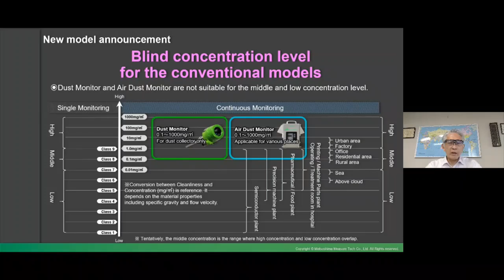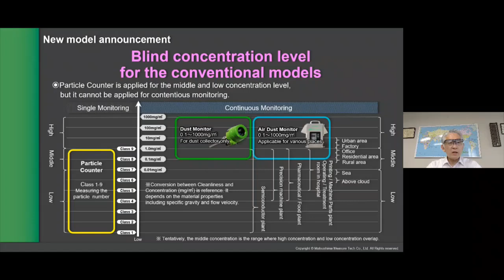Now you see the yellow one. We call these particle counters, general particle counters. Most particle counters are generally for lower concentration clean room applications. And you can see now these three sensors cover most applications. But recently we've noticed that those general particle counters are basically for instant measurement and not for continuous measurement. It means it's difficult to achieve process control with those general particle counters. So that's why we decided to develop a new dust monitoring sensor covering lower concentration but providing continuous measurement signals.